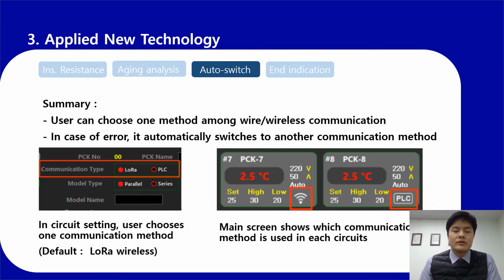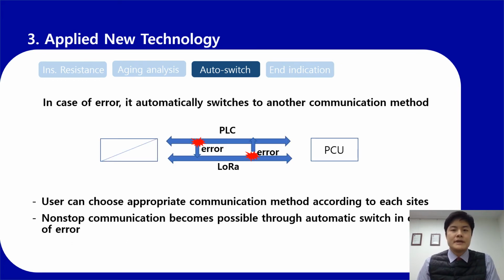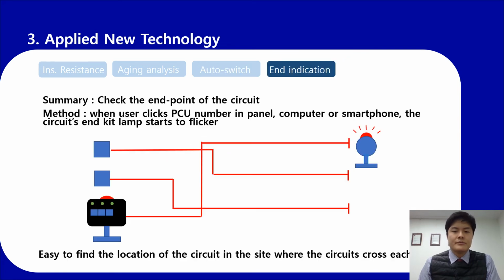I already told you that non-stop communication is very important for energy saving. Our technology uses both wired and wireless communication. The user can choose the appropriate communication method according to the site. Although an error happens in communication, through auto switching, non-stop communication becomes possible. Moreover, our new technology has an end kit lamp flickering function. It helps to check which circuit is connected to which endpoint through which path. The manager can do maintenance with much more convenience.